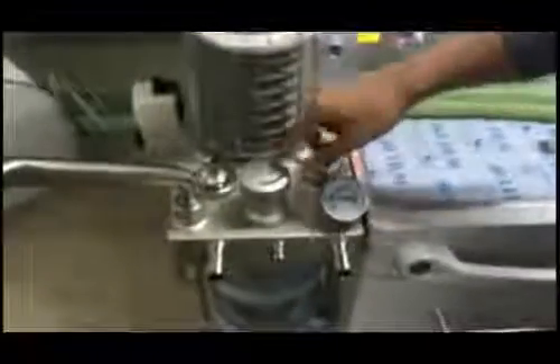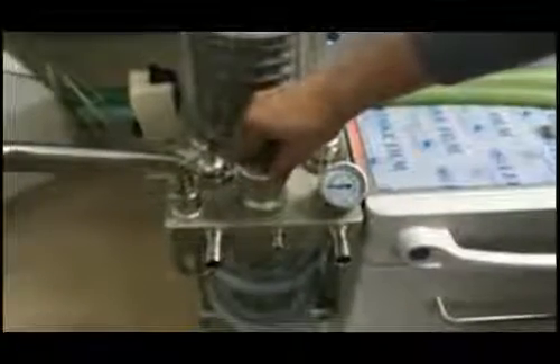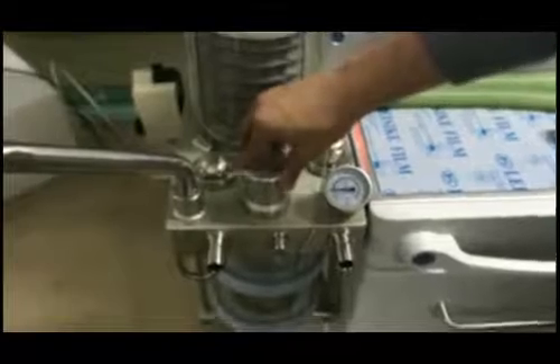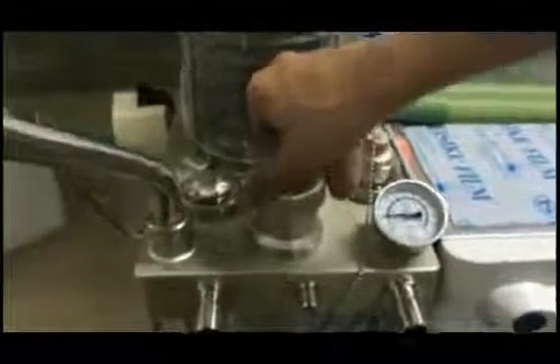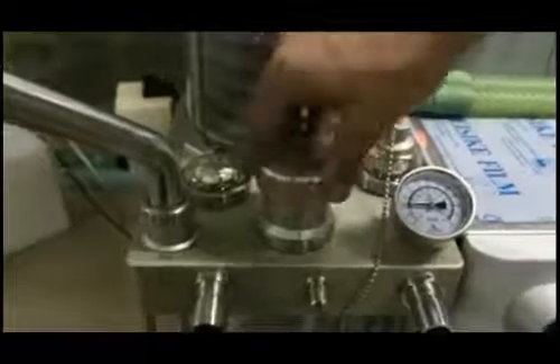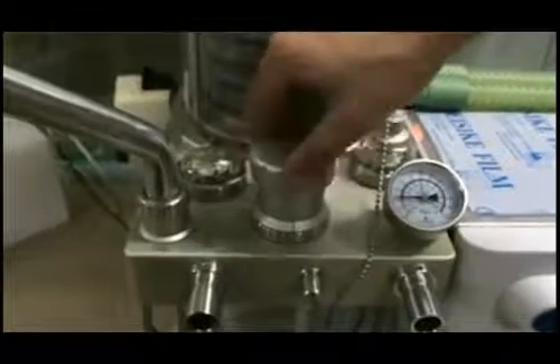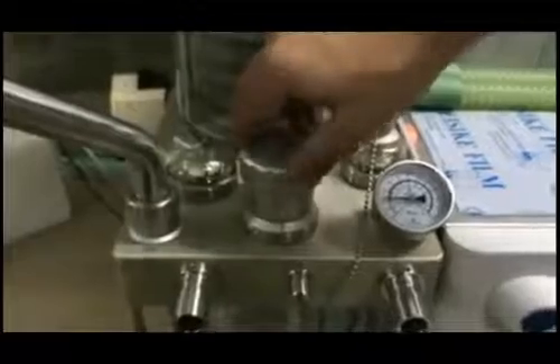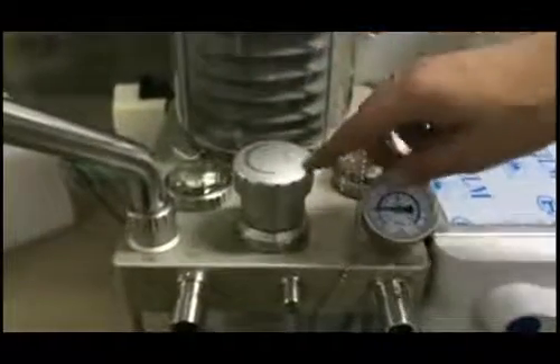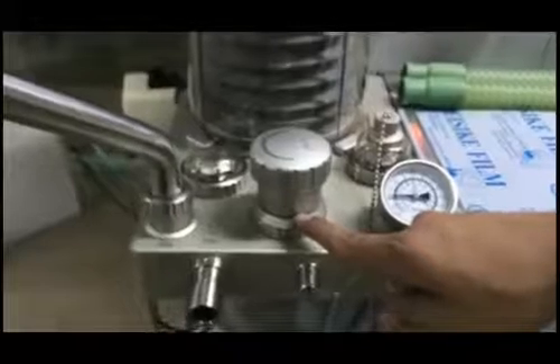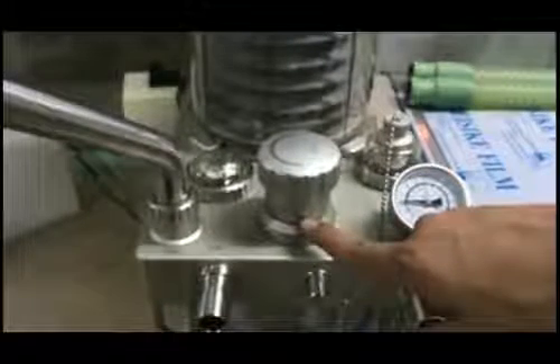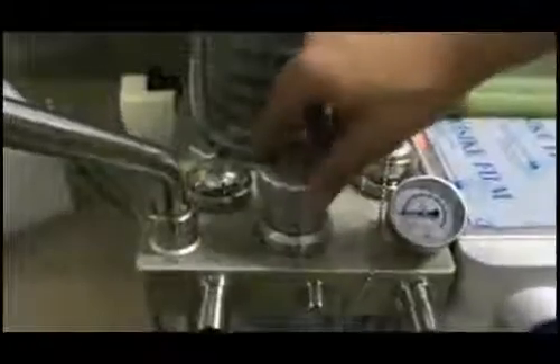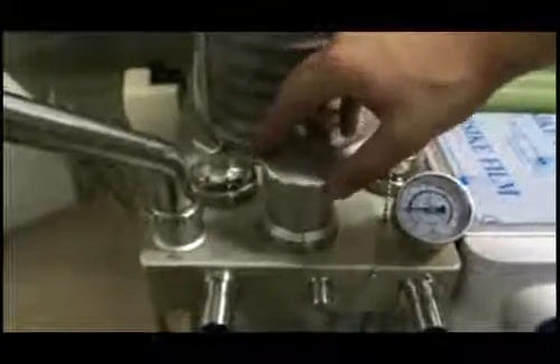The next instruction is set the APL valve to 0. This is the APL valve. The APL valve has different selections: 30, 50, 70. We have to set it to 0. As you can see on the APL valve, the 0 is not displayed, but this point is equal to 0. After you set it into this position, there will be a click sound.